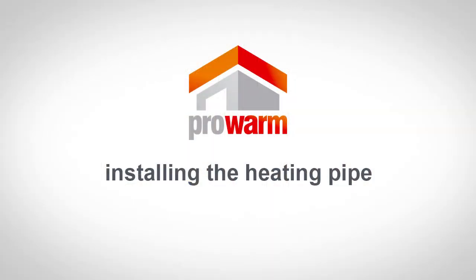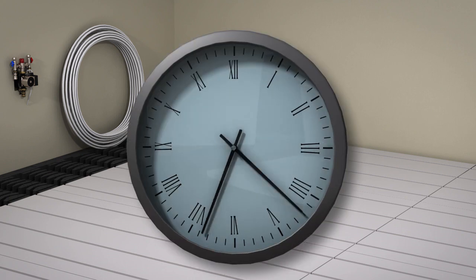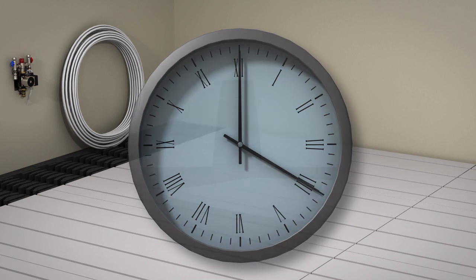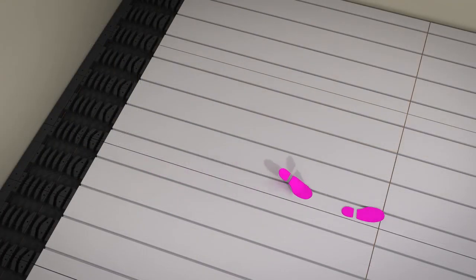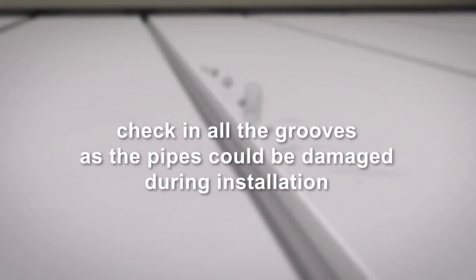Once the installation of the ProWarm overlay panels is complete, you are now ready to install the heating pipe. We recommend giving the glue one to two hours to dry before commencing with the pipe installation. The heating panels can withstand foot traffic without damage to the boards. Ensure your floor is free from any debris before installing the pipe. It is important to check in all the grooves as the pipes could be damaged during installation if there are any obstructions.